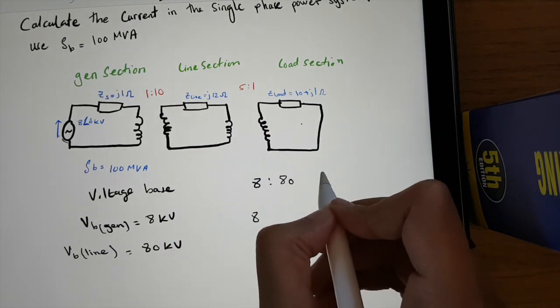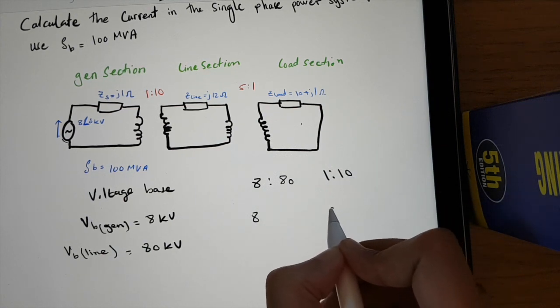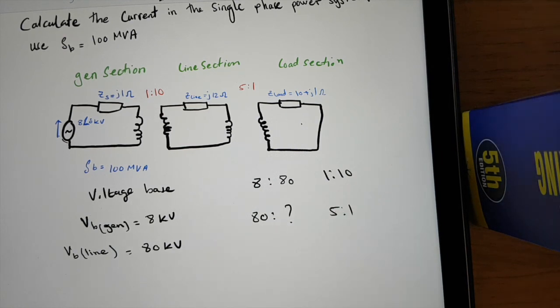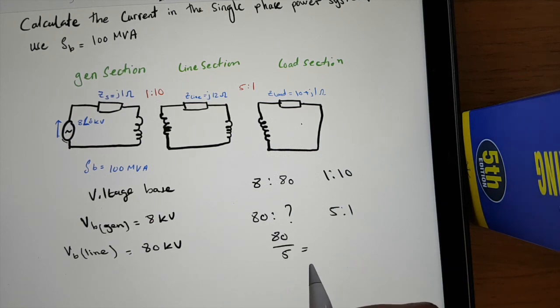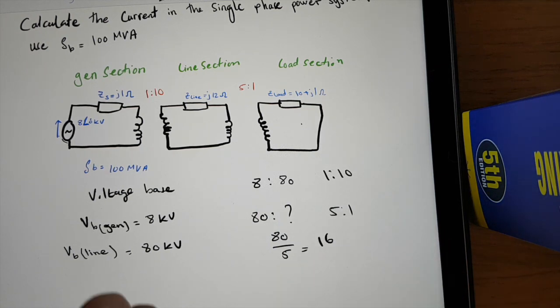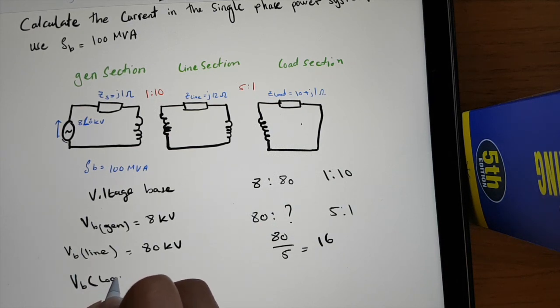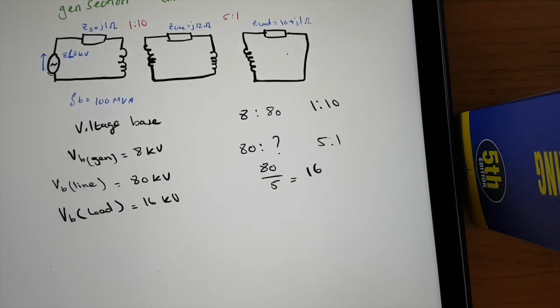For the load section, we have 80 kV on the line side. The step-down transformer has a ratio of 5 to 1, so we do 80 divided by 5, which gives us 16 kV. So V_base for the load section is 16 kV.